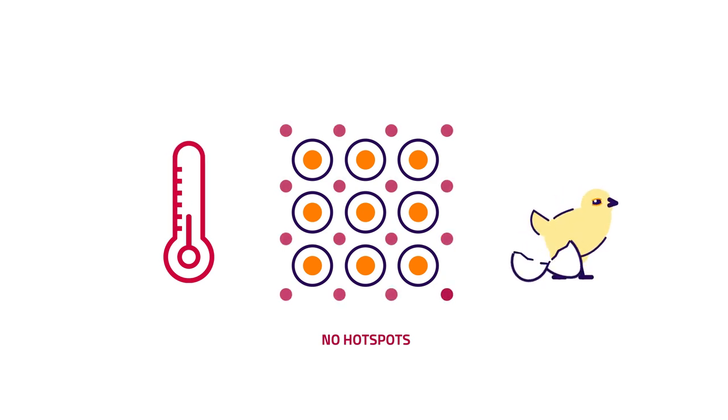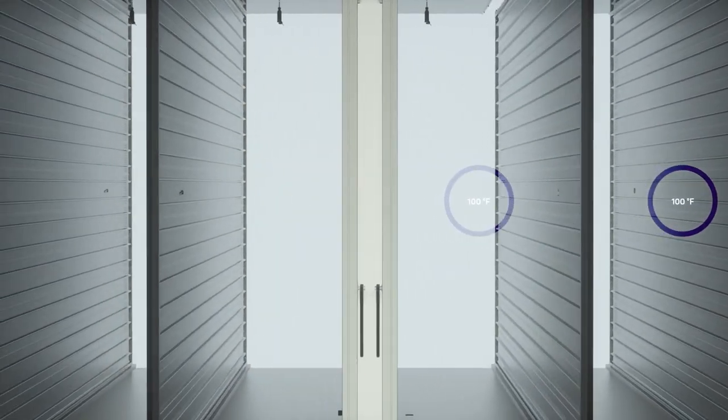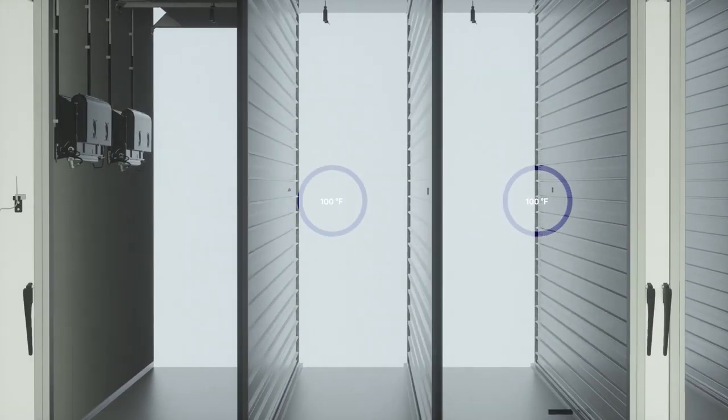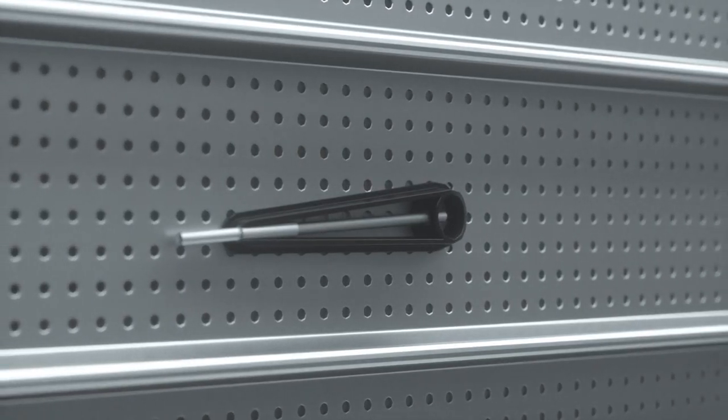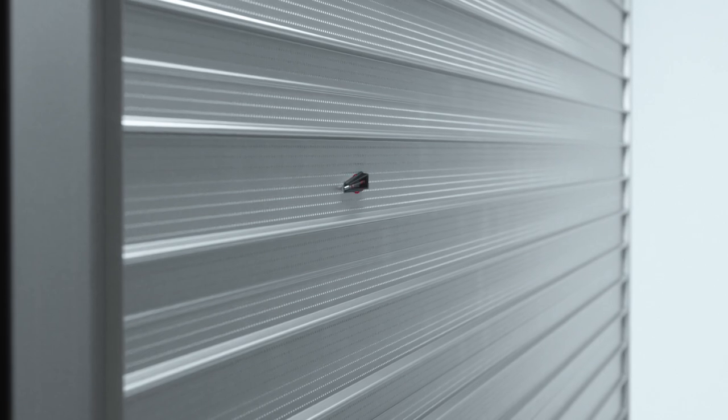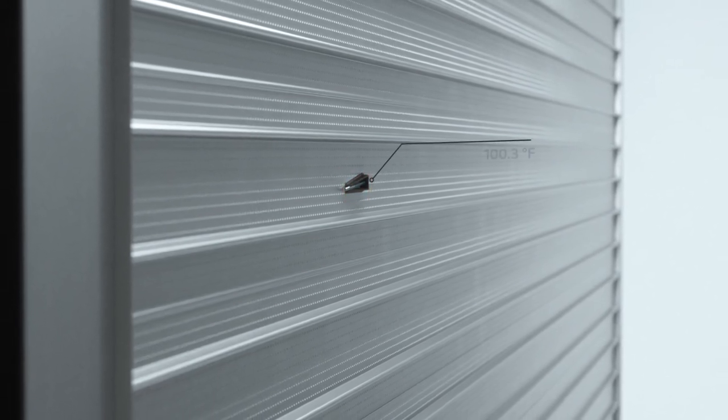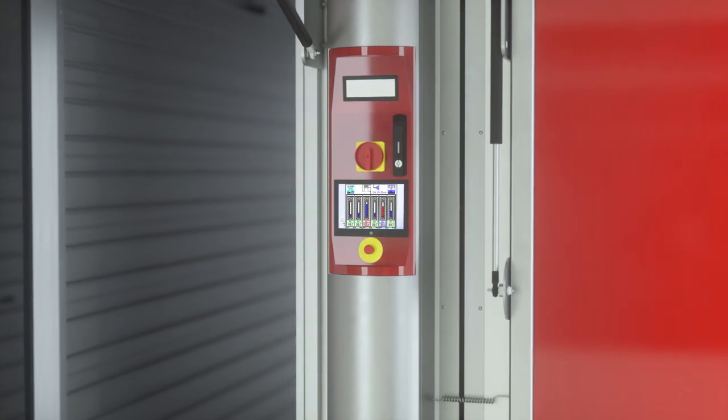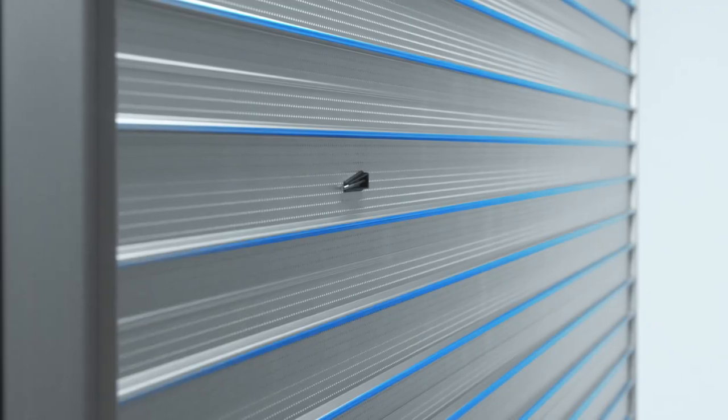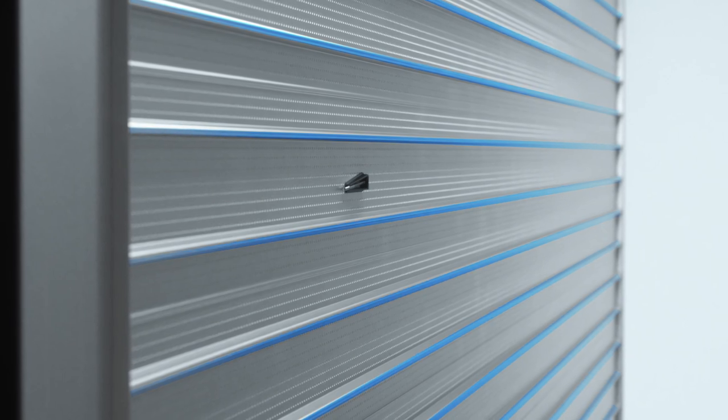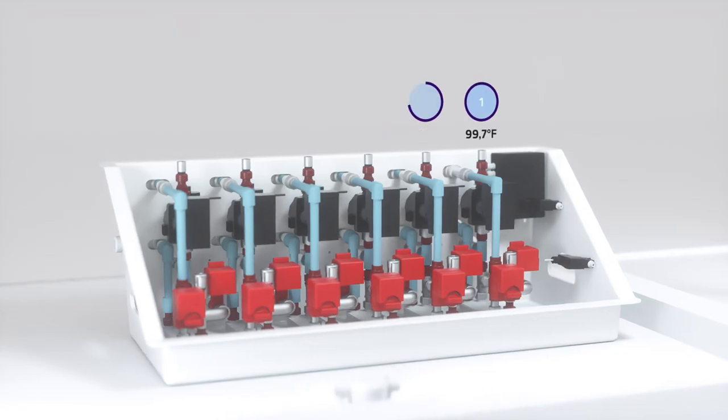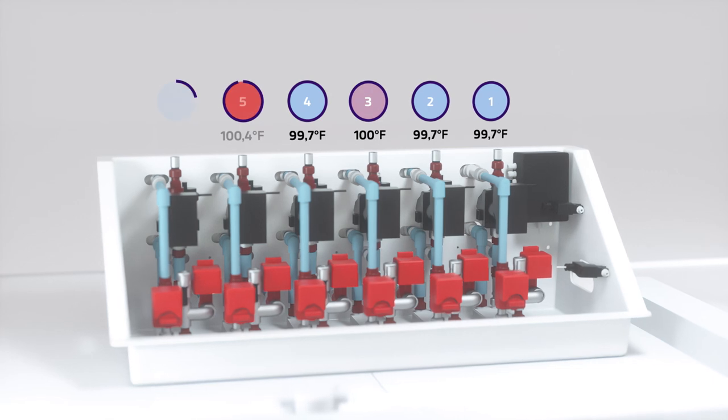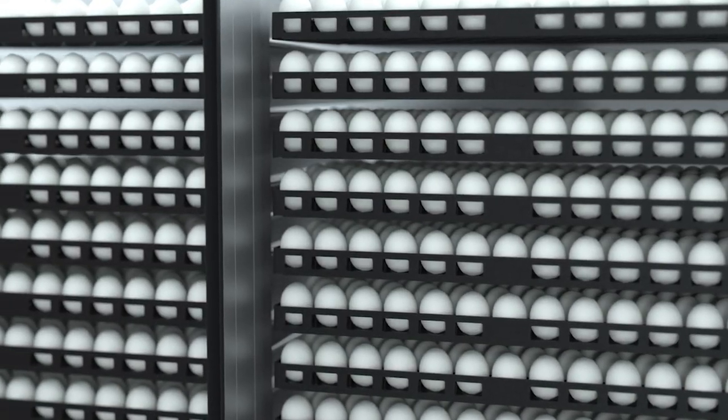To achieve this, HatchTek's unique incubator design enables optimal temperature in each section of the incubator. Each section is equipped with a temperature sensor. Sensor information is constantly sent to the microclimate controller. The controller sends out a heating or cooling signal to each radiator. The radiator in each section is cooled or heated by the water running through it. Modulating heating and cooling valves make it possible to fine-tune the radiator temperature in each section.